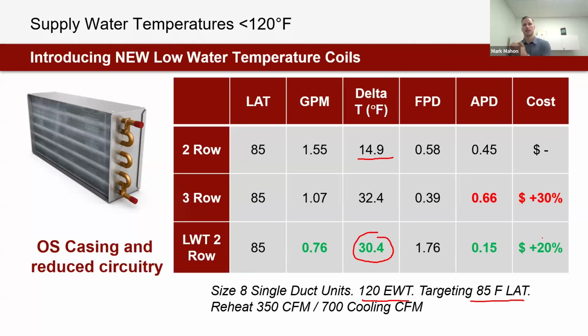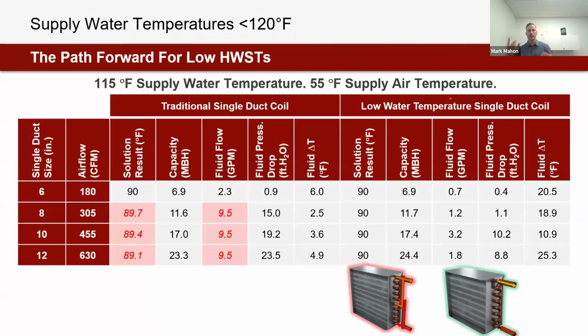So when we look towards systems and where we need to implement a 3-row coil, the thought process is let's go for a 2-row low water temperature coil because we're going to have lower GPM, a larger delta T, and much lower air pressure drop. Now we're suddenly able to both improve the boiler efficiency without totally shooting the air handler and fan efficiency in the foot. And so looking at this in an even more extreme condition here, what I'm targeting here is a 90 degree leaving air temperature, both for the new coils and the old coils. We can see that here.